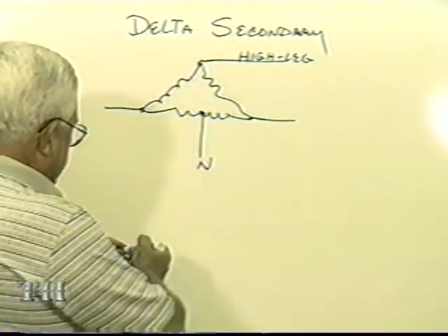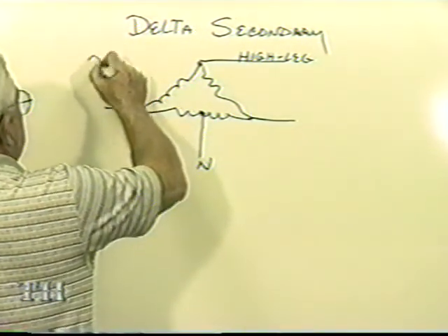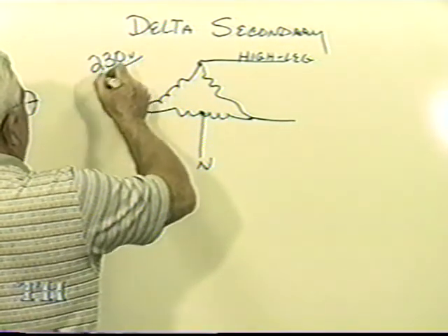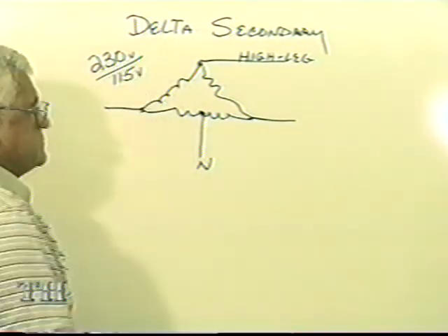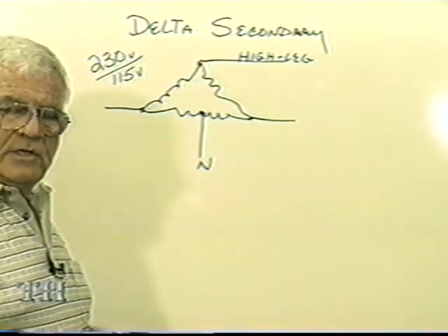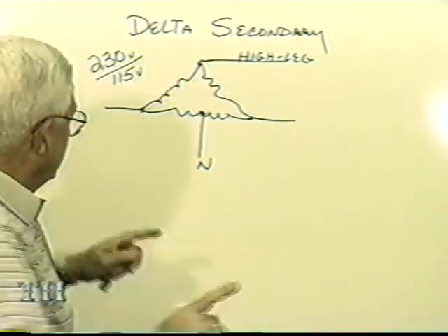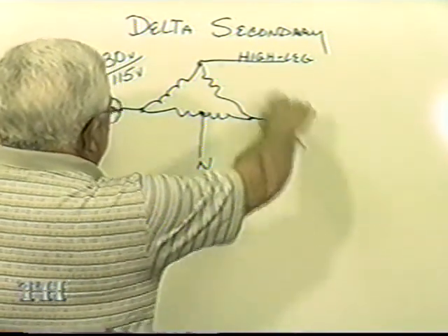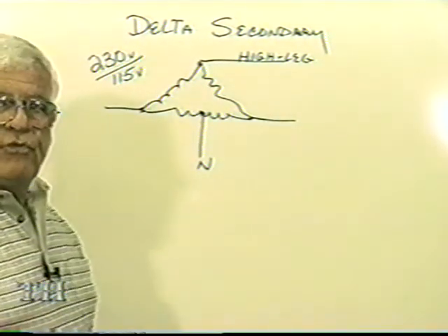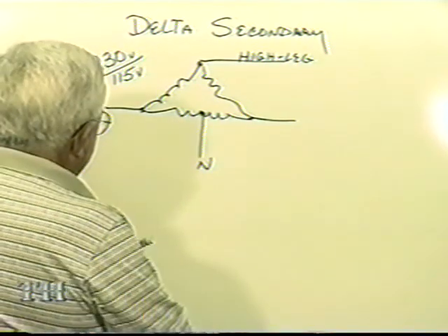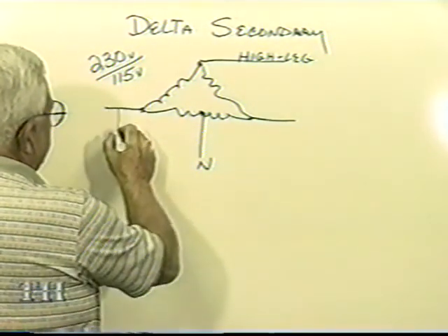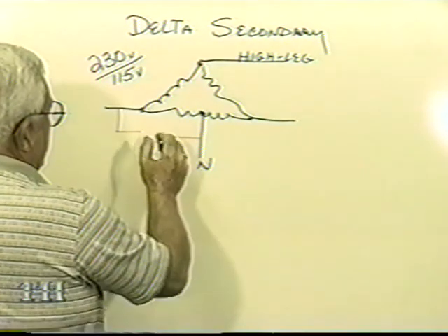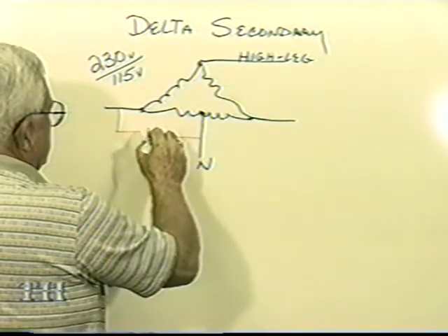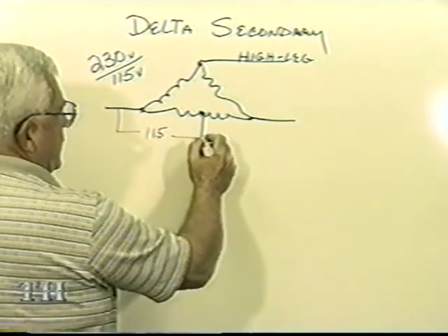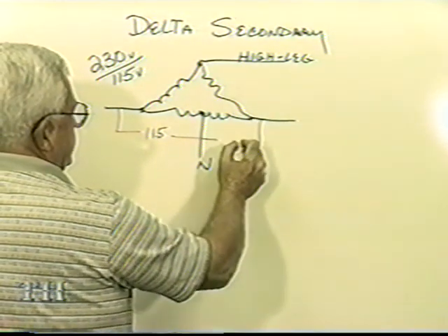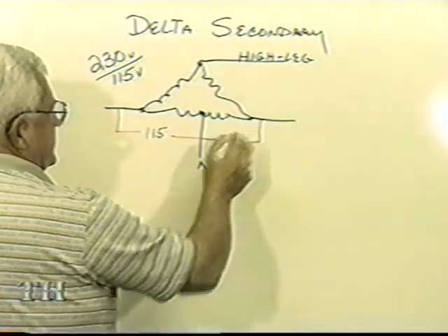See, if you gave us a voltage, let's give it a voltage. Let's say it's 230/115. Well, here comes your voltmeter again, and I want you to keep in your mind the day of the test. If you put your voltmeter from line to line, you've got to read 230. And if you put your voltmeter from here to here, you're going to read 115 volts. Or if you went from here to here with your voltmeter, you're going to read 115 volts.